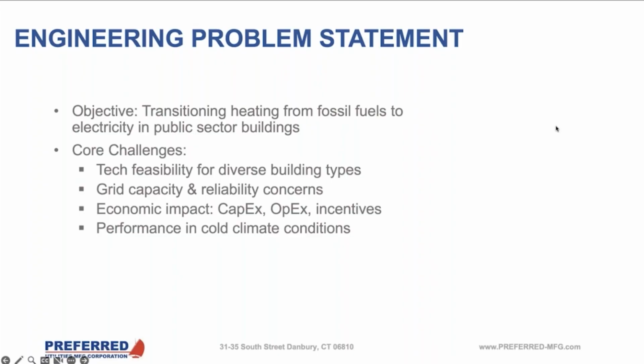So this is a case where technology could eventually catch up and supply New York City on the coldest days - it just becomes a matter of consumption, and also a matter of cost. These systems getting down to lower temperatures use higher pressure refrigeration cycle systems with more expensive components, so it becomes a capital cost issue since the upfront cost to install them gets very expensive. Those are more specialized heat pumps.